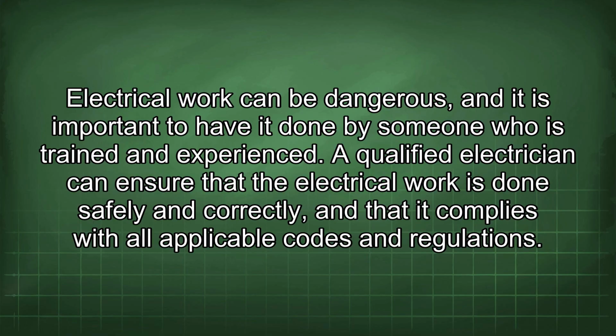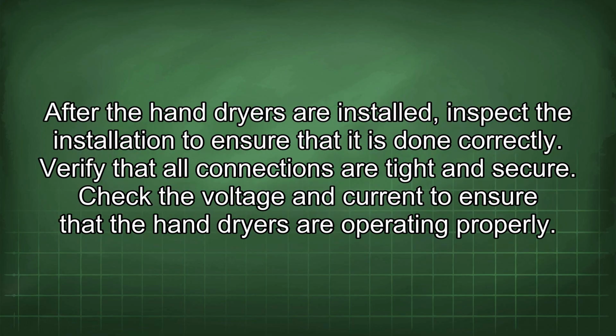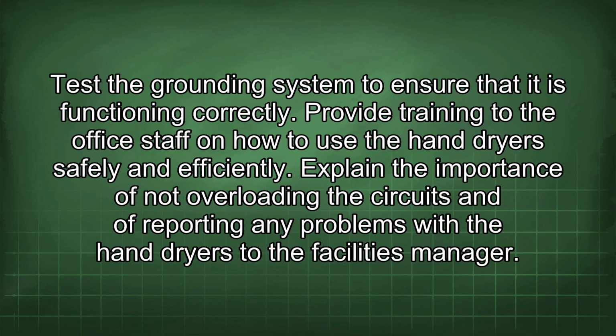A qualified electrician can ensure that the electrical work is done safely and correctly, and that it complies with all applicable codes and regulations. After the hand dryers are installed, inspect the installation to ensure that it is done correctly. Verify that all connections are tight and secure. Check the voltage and current to ensure that the hand dryers are operating properly. Test the grounding system to ensure that it is functioning correctly.